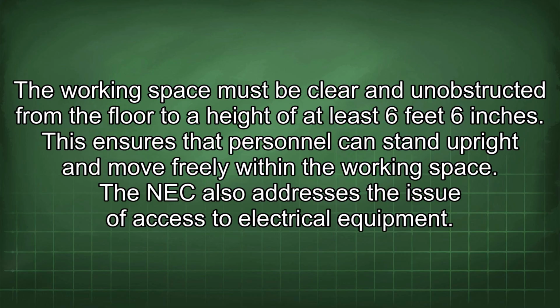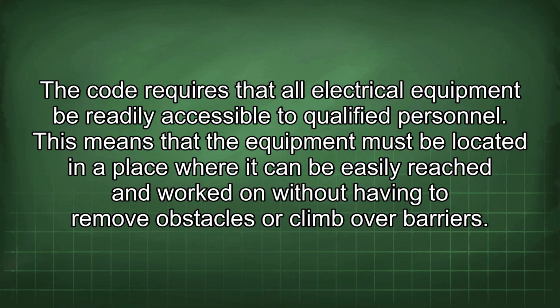The NEC also addresses the issue of access to electrical equipment. The code requires that all electrical equipment be readily accessible to qualified personnel. This means that the equipment must be located in a place where it can be easily reached and worked on without having to remove obstacles or climb over barriers.